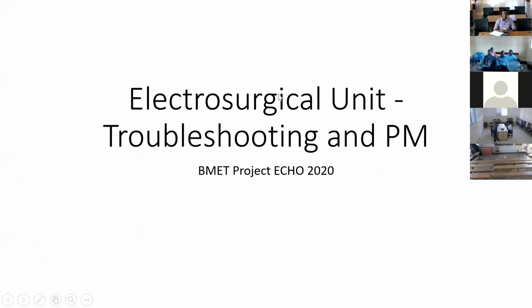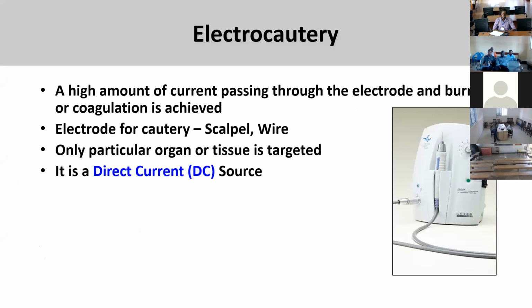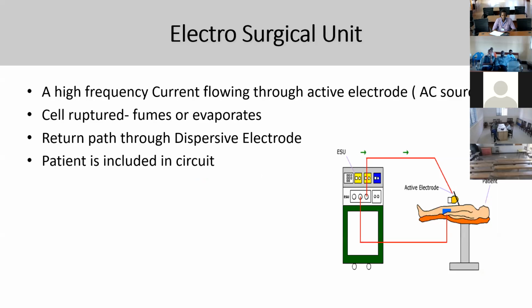Okay, so I'm going to talk about the electrosurgical unit still, but on PM and troubleshooting. When you talk about electrosurgical, everyone knows about electrocautery. It's before the electrosurgical generation. They got electrocautery and electrosurgical, two different devices actually. Cautery is about a direct current, DC source, and it's a limited space. Basically, only a particular organ and tissue are targeted during the surgery. For electrosurgical, you are talking about high frequency current flowing through the active electrode, basically using an AC source but higher frequency. Normal AC source is 50 Hertz, but you are talking about more than 100 kilohertz or 500 kilohertz, depending on the type of electrosurgical unit you are using.